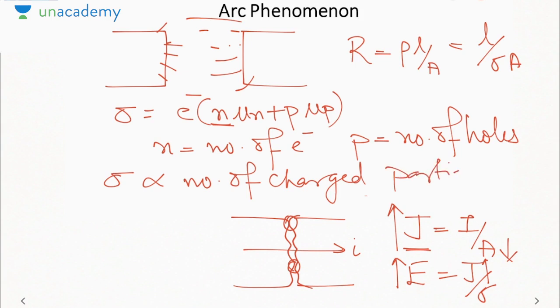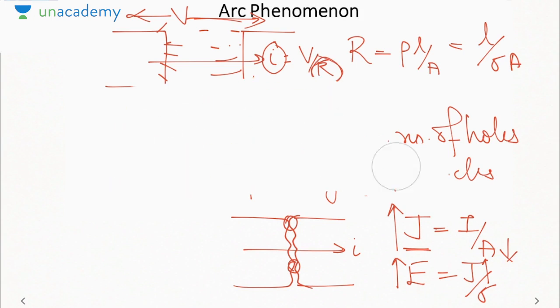Now, in open circuit condition, the voltage across this circuit breaker will be, let us say, V. So the current that will be flowing, I, will be equal to V by R, where R is the resistance of arc and I is the current flowing through the arc. Now we need to reduce this current I to 0 in order to open the circuit. So to reduce this current to 0, we need to gradually increase this resistance. Now to increase this resistance, there are certain methods.